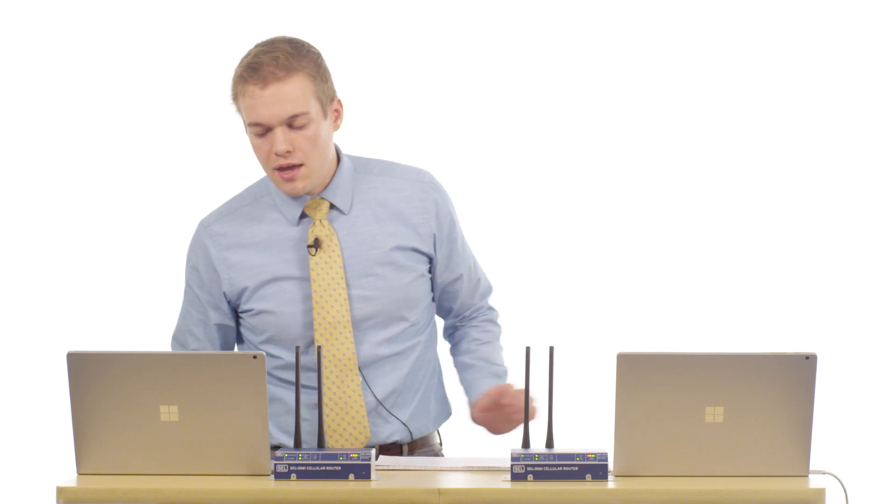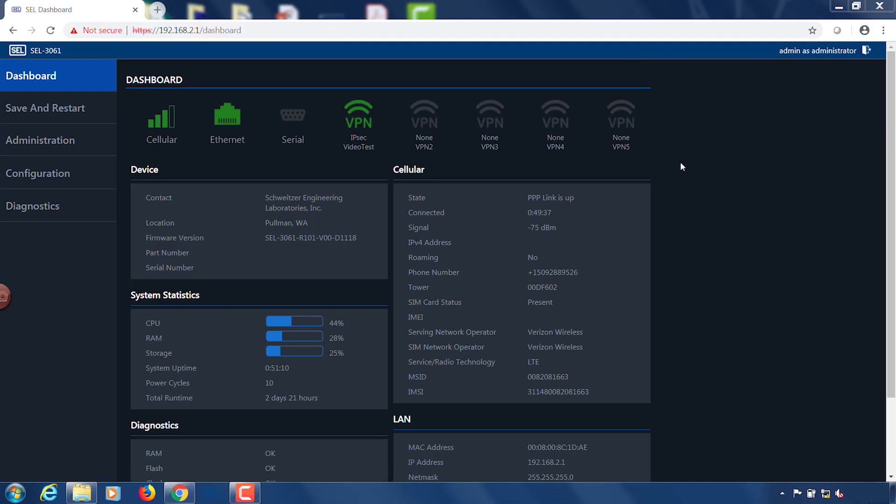Okay now that we have all of the settings complete on both of our SEL 3061 routers we're going to be able to run a ping test where we ping the laptop on side B from the laptop on side A. Before we get into that let's walk through the dashboard a little bit more. You'll see now that the VPN light is lit up indicating that we have a secure VPN connection between the two cellular routers. So we know that while we're passing this IP traffic as part of the ping test it is secure.